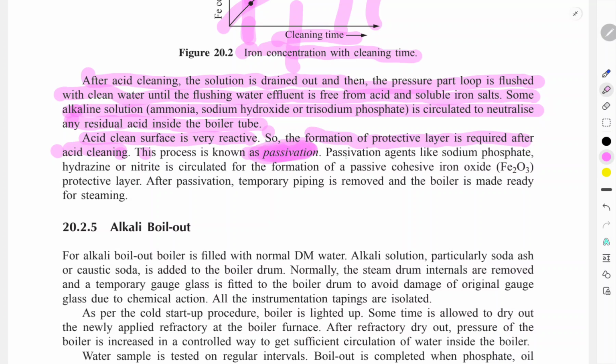Okay, passivation. The passivation agent, like sodium phosphate and hydrazine or nitrite, is circulated in the boiler to form a passive, cohesive iron oxide, Fe3O4, protecting layer. After the passivation, the temporary piping is removed. The boiler is then made ready for steam.